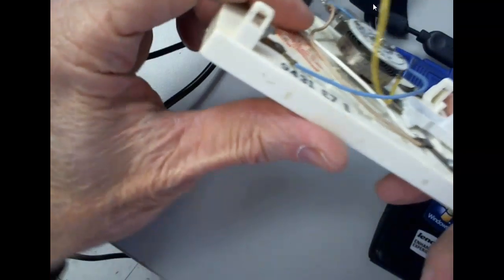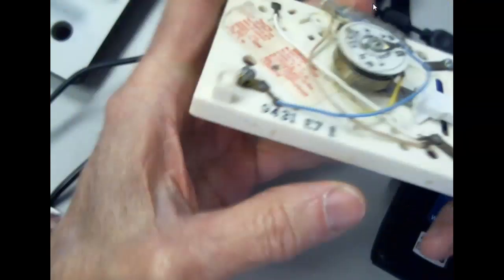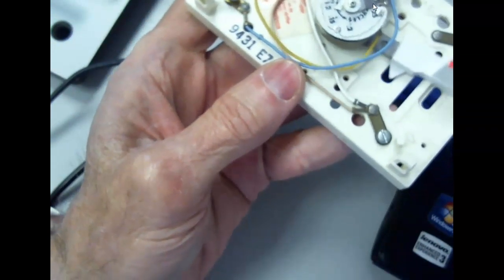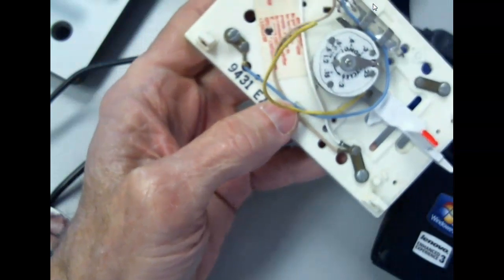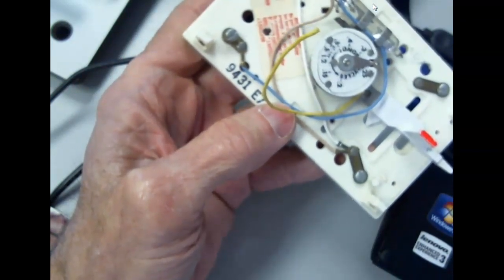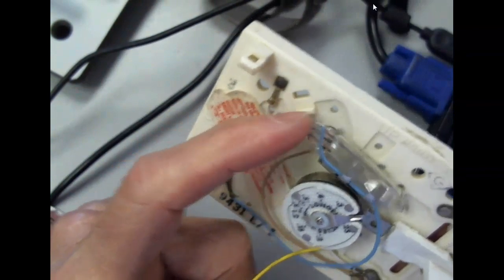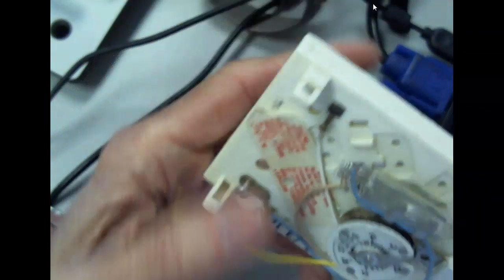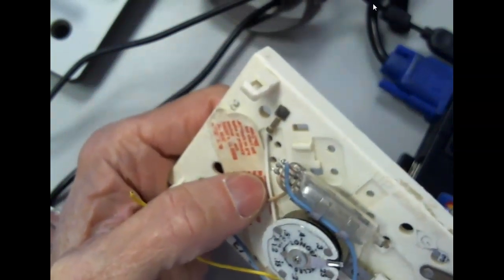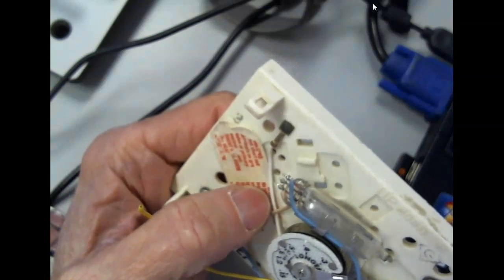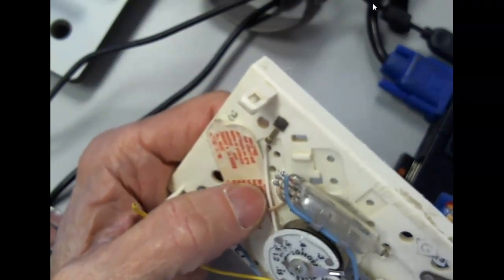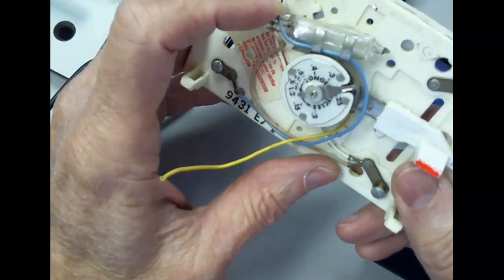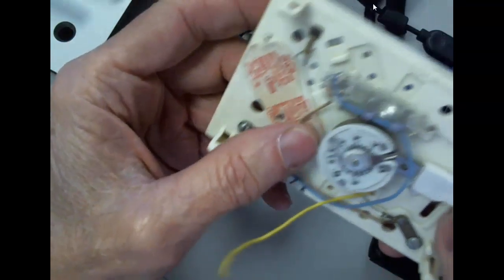So what we're doing is, here's the bimetallic strip right here, and then it's wound. And what we do is we either put more tension on it or less tension on it against a calibrated spring. And when it tries to move, the calibrated spring is either going to make it move slower or faster. And then we had a mercury switch up here. Now, I know mercury is a metal. It's a pretty good conductor, but mercury has an extremely low melting temperature. So when we usually see mercury, it's already what? It's already melted. You can see the little prongs here, and when the mercury goes over them, it covers them up, which creates a circuit. And we used these things for years until they found out what?